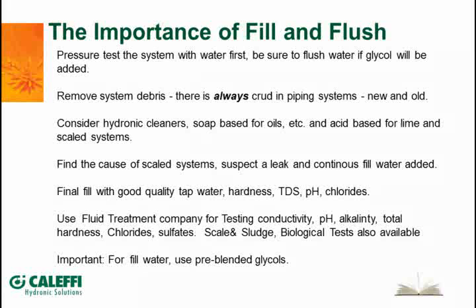And also the last thing that's important, if you're going to use a glycol, I would say use a pre-blended glycol, because that's going to be blended at the factory with a good quality water, so you don't have to worry about taking it on a job where the water on the job site isn't good enough and is going to start to break down some of the inhibitors in your glycol. So use a pre-blended. You can find it out there. It's usually going to be blended about 50% water to glycol, and that gives you pretty good freeze protection in most spots.